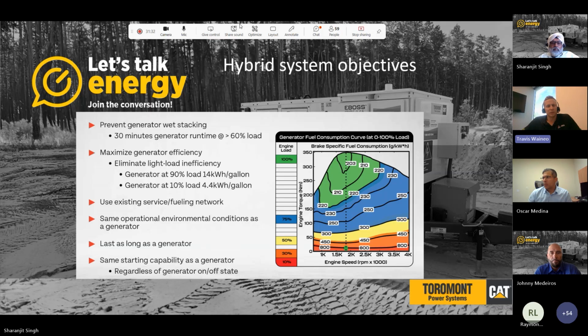The other really interesting point is we like to utilize the existing service and fueling network. If you're used to rolling a diesel truck on site every day or every few days, depending on the job, to fuel up other equipment, let's use that same fueling network. I don't necessarily want to have to tow a battery on site, run it, and then tow it back off. That's not using the existing network. You'd have to build a new infrastructure and fueling network for that. So let's use the existing fueling network that's already on site, a diesel truck, and then service as well, right? You have diesel maintenance techs that go out and do oil changes and stuff. Let's try to use that infrastructure as much as possible when we build a hybrid system.